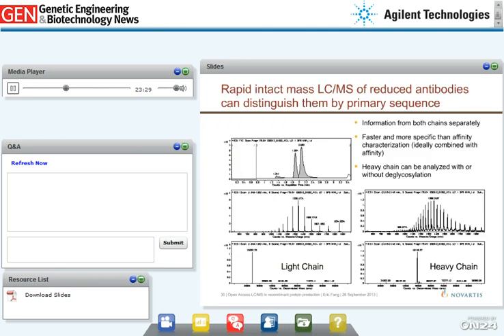To focus on antibodies for a moment, many labs produce many different IgG antibodies with different primary sequences that you can't distinguish on a gel. Many labs will confirm by affinity measurement, which is useful and desirable, but realistically you don't have the same speed or resolution as reduced antibody intact mass. You can confirm the expected primary sequence of both heavy and light chains if you have a known sequence, allowing for stereotypical modifications like pyroglutamate formation, lysine loss, and glycosylation. Without deglycosylation, you can do this very quickly — in just minutes. Deglycosylation is generally helpful because it reduces the number of variations to consider, and all data analysis can be done automatically after sample submission.